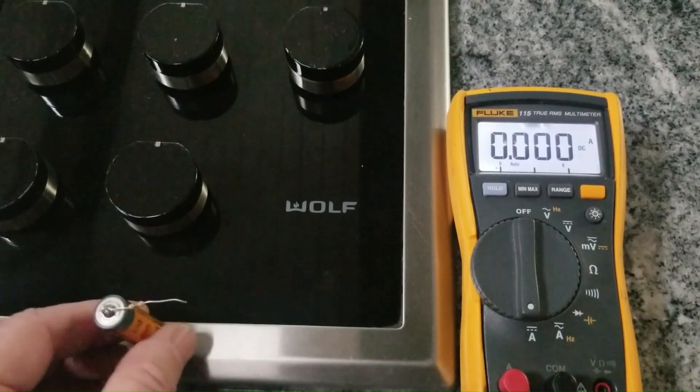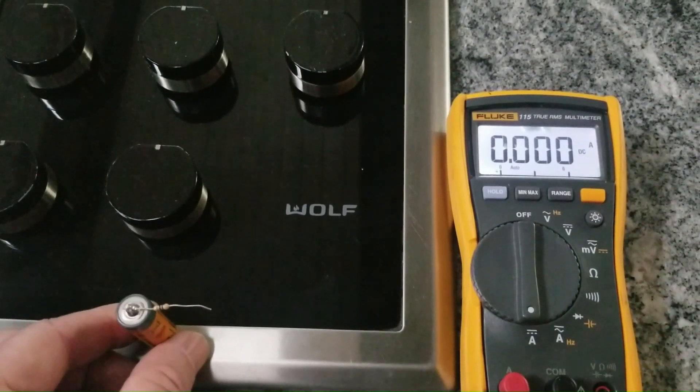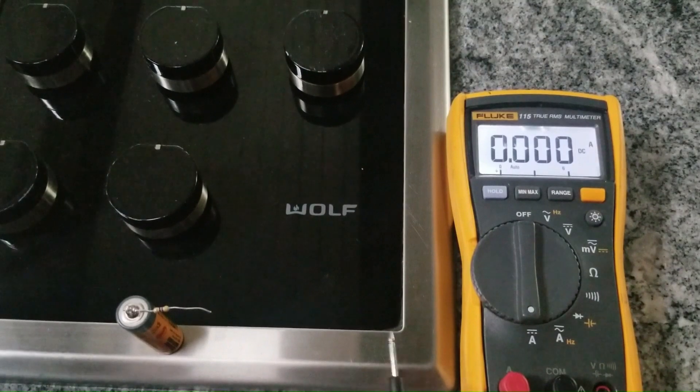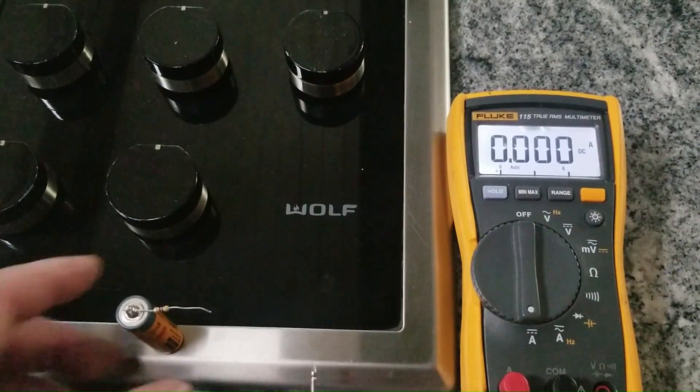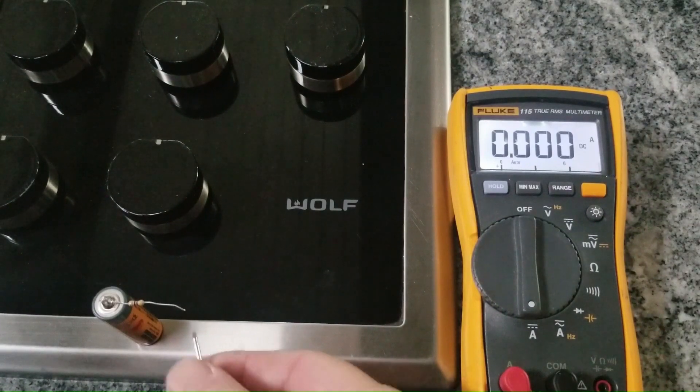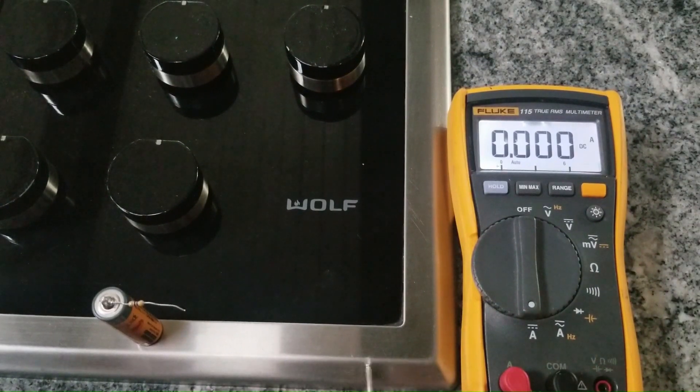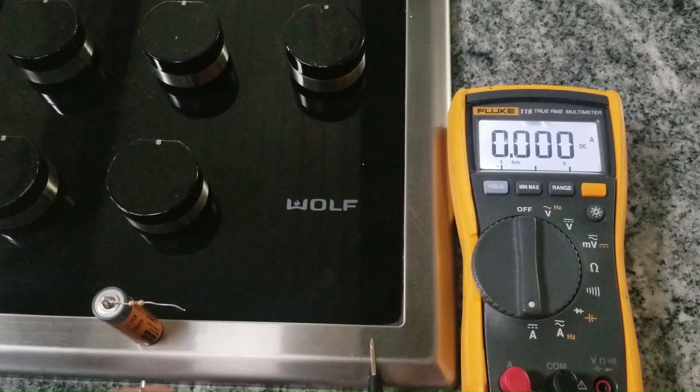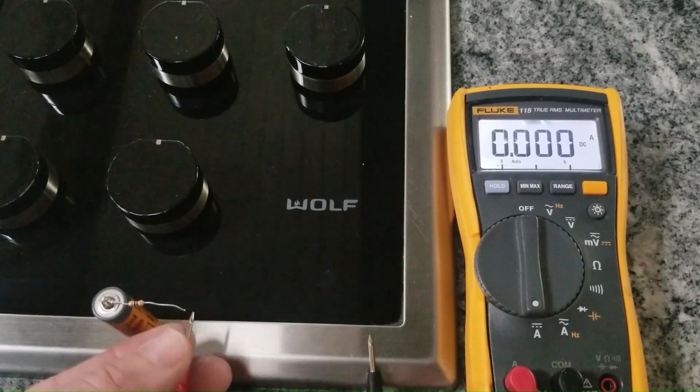Instead, I'm placing this battery on the chassis of a cooktop that is connected on a GFCI circuit. I'm going to pass this current through the chassis. One side of the battery is connected to the chassis, and the other side through this resistor, and I'm going to place this lead on the chassis, and current is going to flow into the chassis.